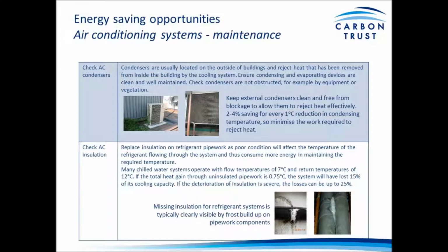So in this instance the energy loss is 15%, but if the deterioration of insulation is severe, losses can be much more significant. So it's well worth insulating your pipework to a high standard to minimize your losses and reduce the load on your cooling plant.